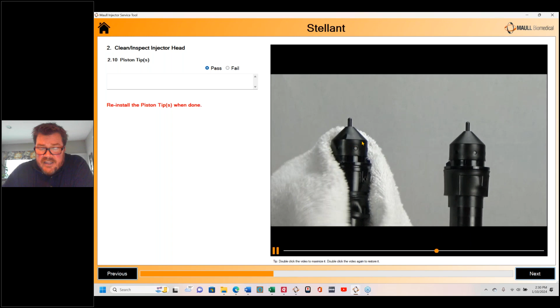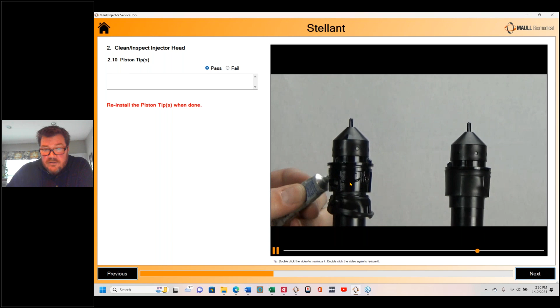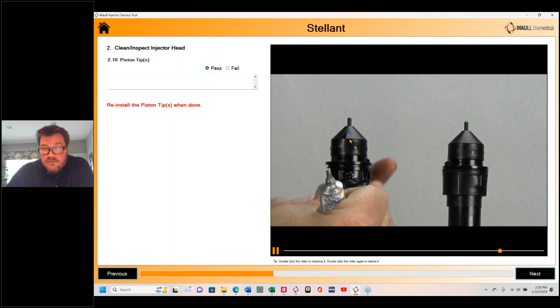This is just going over the piston sleeve and the rubber piston boot that are basically there just to help keep any contrast that does get spilled on there from getting inside the tip. Same thing, we're just going to use some sort of dielectric grease on the tips, and it just helps keep the boot soft and keeps it from slipping away. And if there is a contrast spill that gets to it, if it's covered in grease, it tends to keep the contrast out.